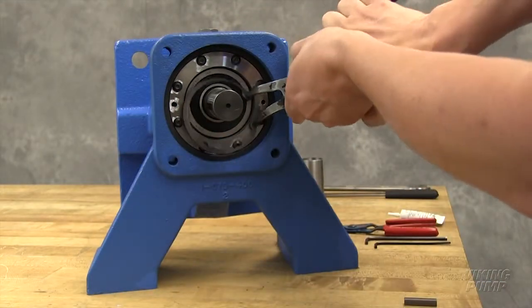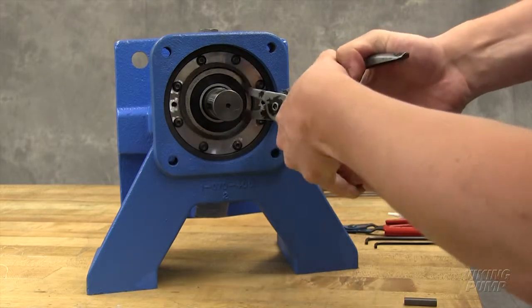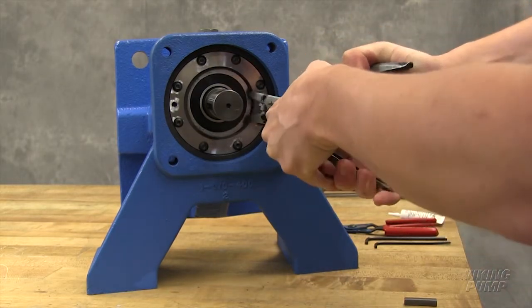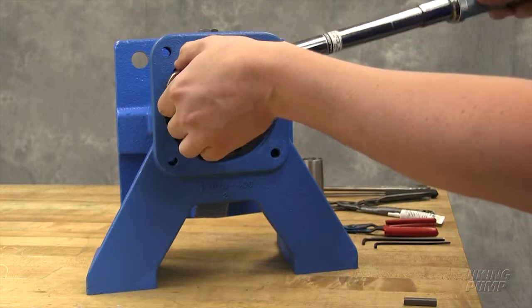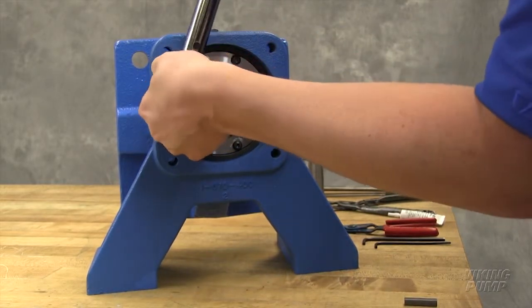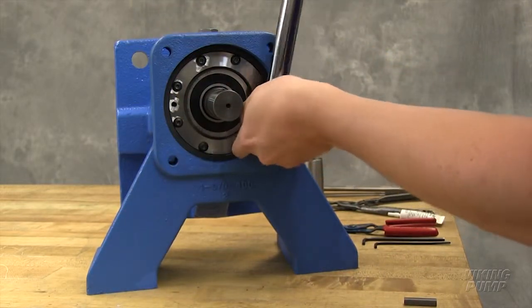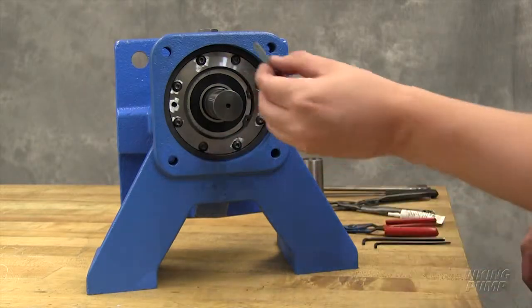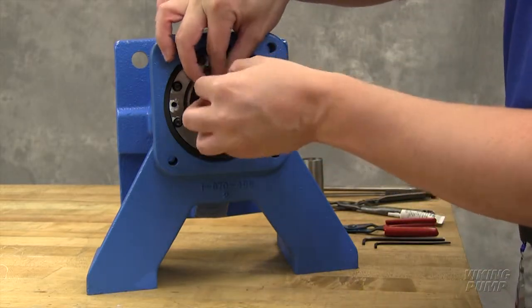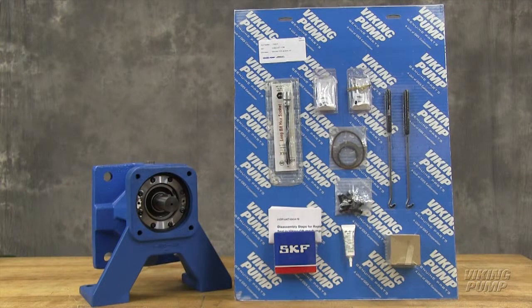Install the retaining ring into the groove of the seal holder. Tighten the cap screws in a star pattern. Torque to 96 inch-pounds. Install the drive key into the shaft. Your Viking pump external gear pump has a new mechanical seal and is ready to be put back into service. Follow the suggested maintenance located in the appropriate technical service manual for a long, trouble-free service life.